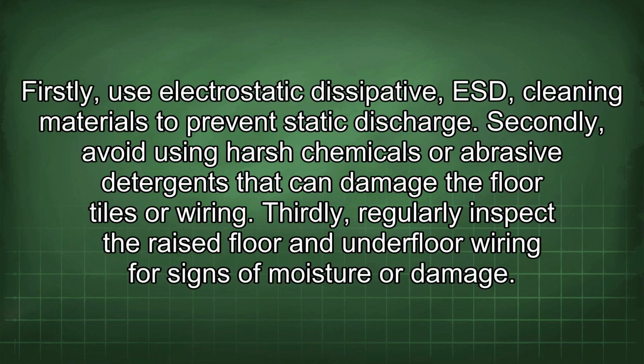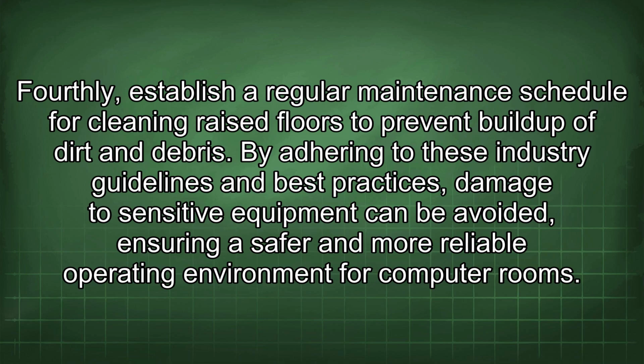Firstly, use electrostatic dissipative ESD cleaning materials to prevent static discharge. Secondly, avoid using harsh chemicals or abrasive detergents that can damage the floor tiles or wiring. Thirdly, regularly inspect the raised floor and underfloor wiring for signs of moisture or damage. Fourthly, establish a regular maintenance schedule for cleaning raised floors to prevent buildup of dirt and debris. By adhering to these industry guidelines and best practices, damage to sensitive equipment can be avoided, ensuring a safer and more reliable operating environment for computer rooms.